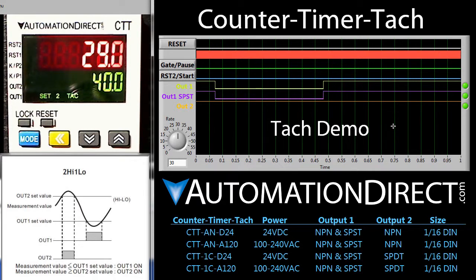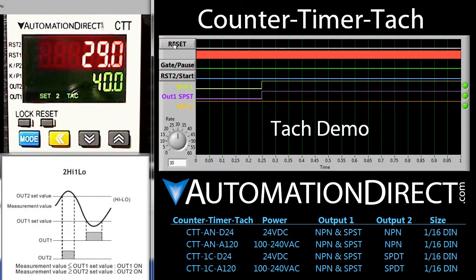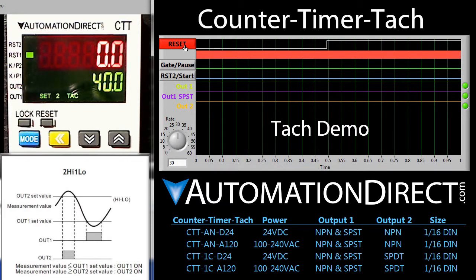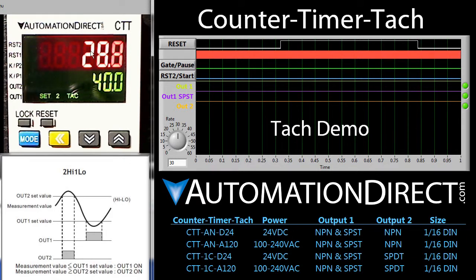What happens if we activate the reset signal? Let's try that – we'll force the reset signal. You can see the little indicator here on the TAC indicating that reset 1 is active. The TAC shuts down. When we release the reset signal, that little indicator goes away and the TAC starts right back up again.